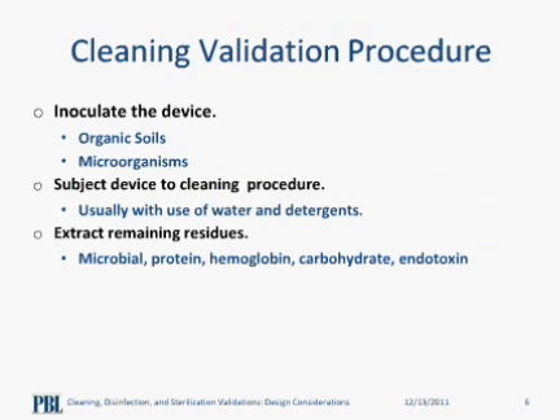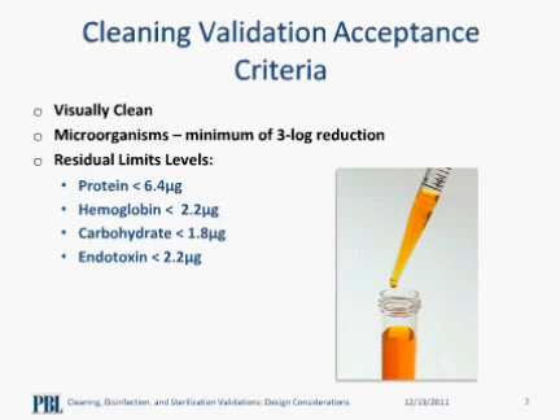After introduction of soils, we subject the device to the recommended cleaning procedure. This procedure usually involves cleaning with water and detergents, but the recommended procedure can be suggested by the chemical manufacturer or established between the sponsor and the consulting lab. After we have cleaned the devices, we extract and quantitate residuals remaining on the cleaned devices. There are a few ways we can go about recovering the residuals, which can include a microbial test, also known as bioburden, protein, hemoglobin, and so on. Based on the results from the recovery, we can determine whether the validation has passed.